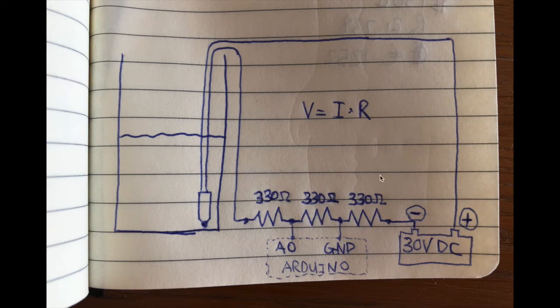Now let's talk about the 2 resistors to the left and right of the center resistor. They're simply there to provide a voltage drop so the water level sensor sees around 24 volts DC, its operating voltage. Since the sensor outputs between 4 and 20 milliamps, the voltage drop over these resistors will vary as the current changes. However, the sensor can operate over a fairly wide range, so we just want to keep it centered around 24 volts.